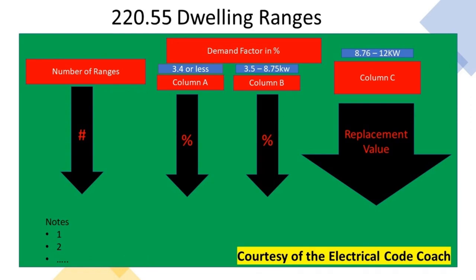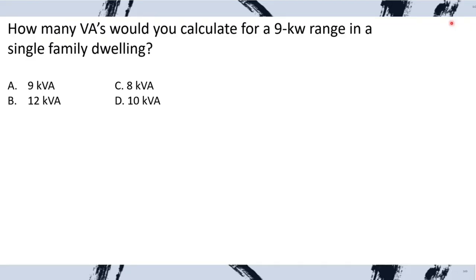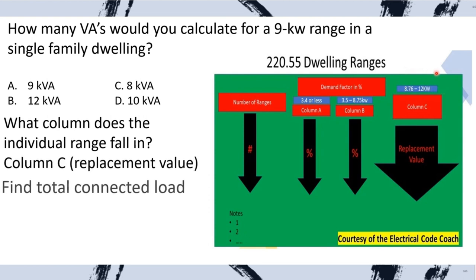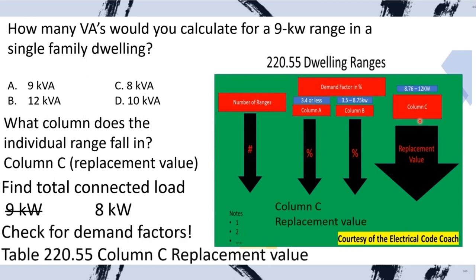Practice problem: How many VAs for a 9 KW range in a single-family dwelling? First, what column does our individual range fall in? It's 9 KW, so it falls into Column C — greater than 8.76 but not over 12. Column C is a replacement value. Find the number of ranges on the left-hand side: 1. Cross over to Column C: the replacement value is 8 KW. Column C is not a multiplier, so there are no demand factors to apply. We select C.